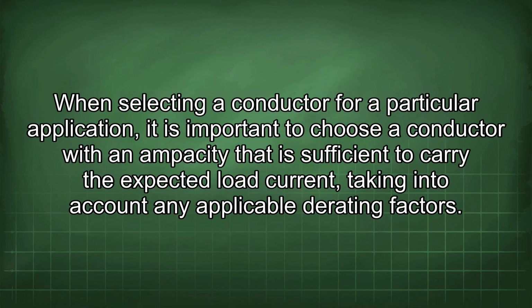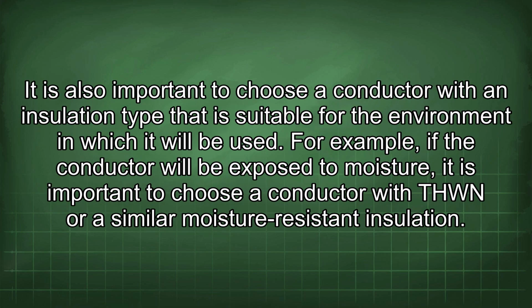When selecting a conductor for a particular application, it is important to choose a conductor with an ampacity that is sufficient to carry the expected load current, taking into account any applicable derating factors. It is also important to choose a conductor with an insulation type that is suitable for the environment in which it will be used. For example, if the conductor will be exposed to moisture, it is important to choose a conductor with THWN or a similar moisture-resistant insulation.